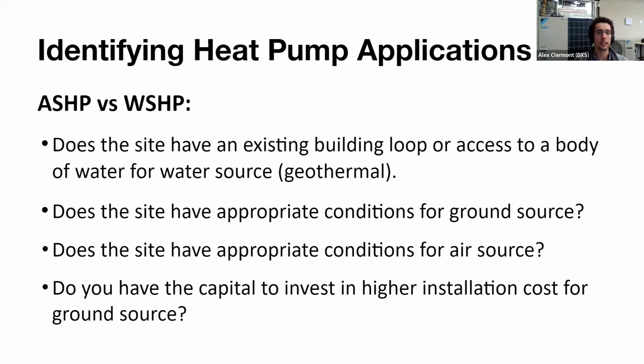Now, don't forget the term water source heat pump often gets used for the typical system used in a downtown Boston 10-story apartment building, where every suite has a water source heat pump that's being fed from a gas-fired boiler and a cooling tower. But for an all-electric building, it actually needs to be geothermal. The loop needs to be geothermal. And that's where the higher capital cost actually comes into play.